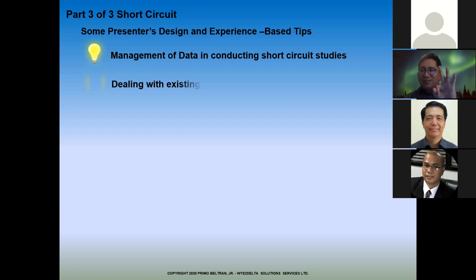When only three generators are running, the reactor is shorted out. Then the moment the 4th generator starts up, I switch in the reactor, meaning my reactor isn't always active - bypassed by a breaker, sir? Yeah, bypass using a breaker.